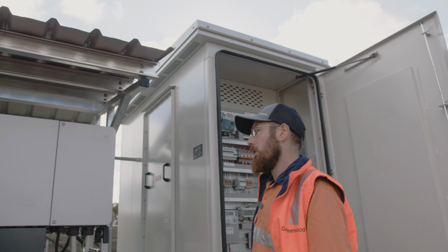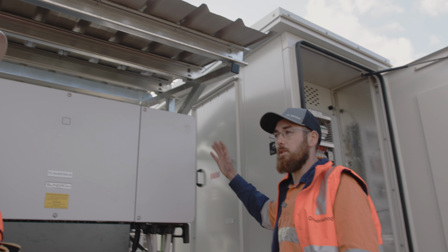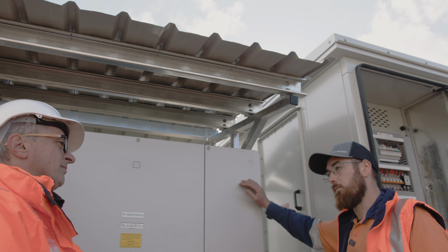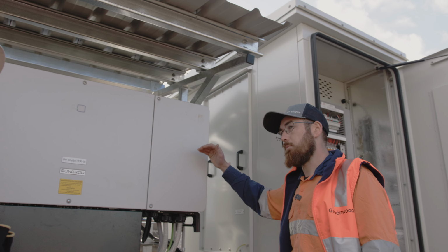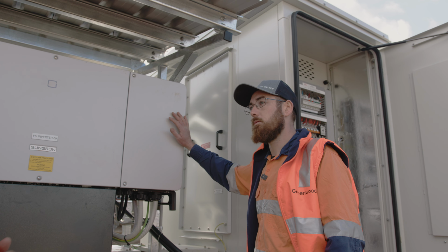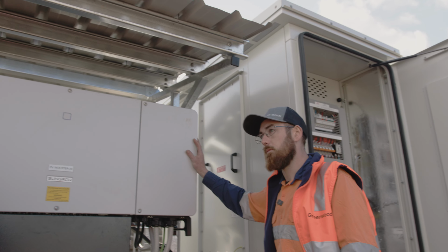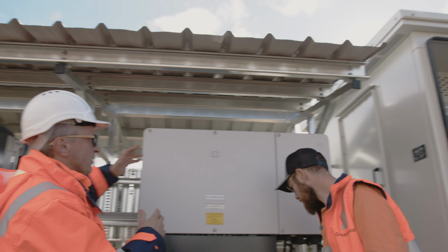Yes, even though they have an IP rating to be out in the weather, it is best practice to cover the inverters, because if they get hot from direct sunlight they will derate themselves. So for best production out of the system, we have a roof which will not only keep the system cleaner and keep the water off it, it actually makes the system produce better. People who see it wouldn't realise why there's a roof over it.